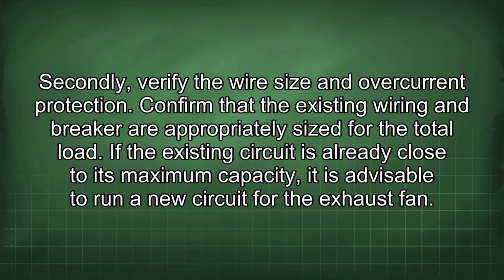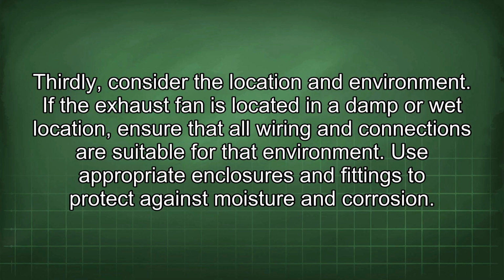Secondly, verify the wire size and overcurrent protection. Confirm that the existing wiring and breaker are appropriately sized for the total load. If the existing circuit is already close to its maximum capacity, it is advisable to run a new circuit for the exhaust fan. Thirdly, consider the location and environment. If the exhaust fan is located in a damp or wet location, ensure that all wiring and connections are suitable for that environment. Use appropriate enclosures and fittings to protect against moisture and corrosion.